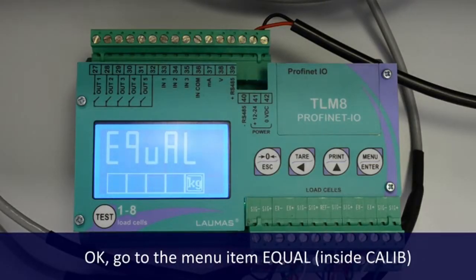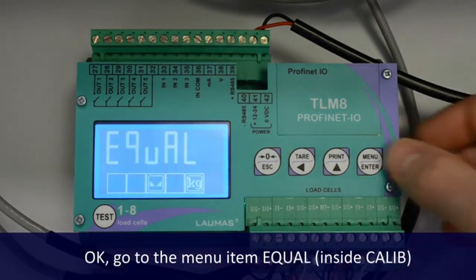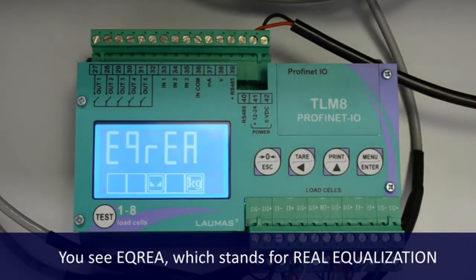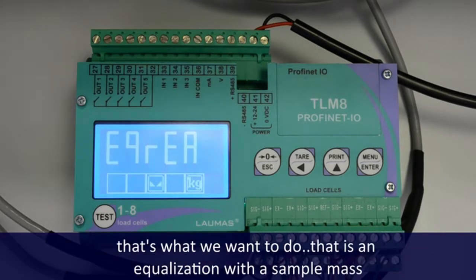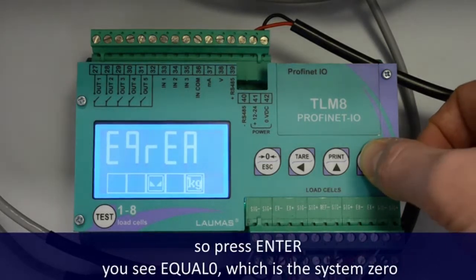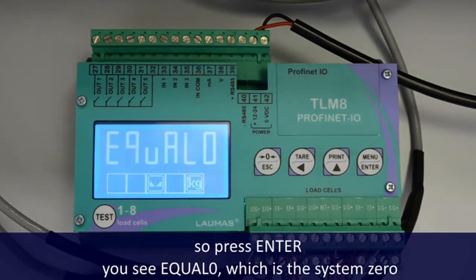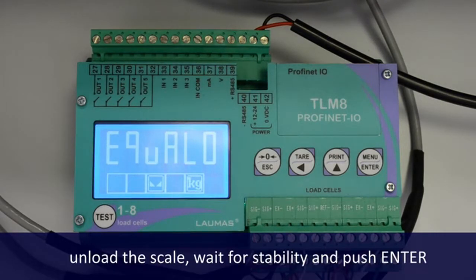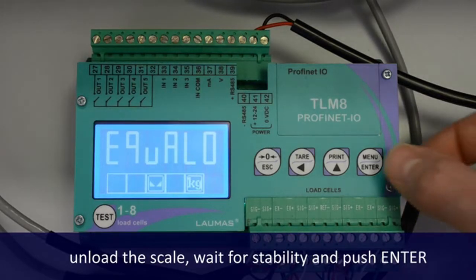Okay, go to the menu item Equal inside Calib, press Enter. You see EQREA, which stands for Real Equalization. That's what we want to do. That is an equalization with a sample mass. So press Enter. You see equal 0, which is the system 0. Unload the scale, wait for stability and push Enter.